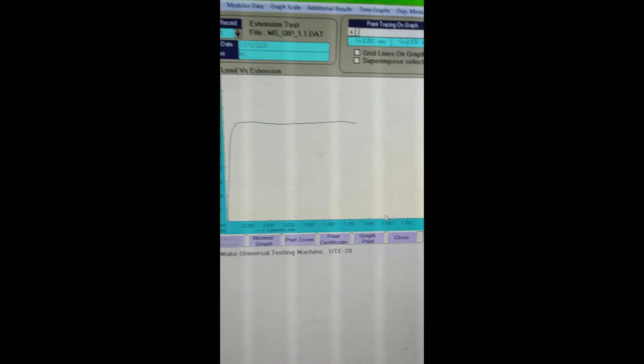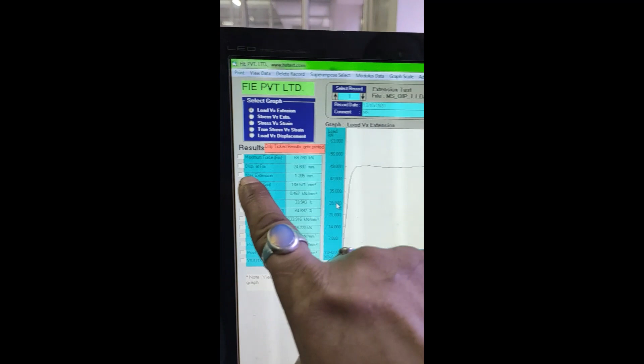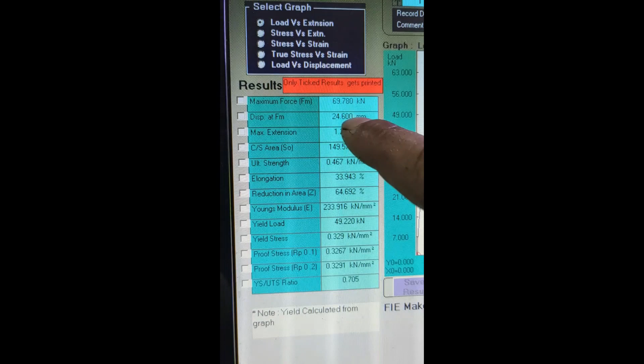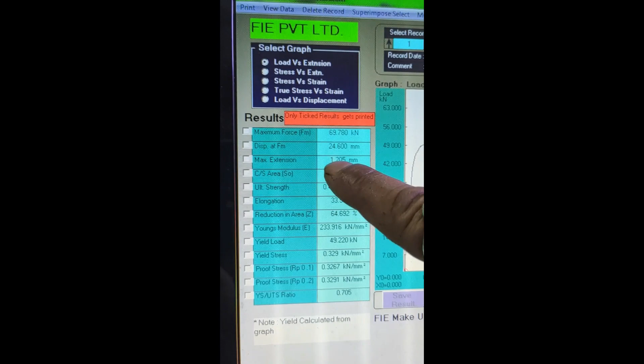This value we will put in, and we will put some MS, then we will close it, then the results will be saved. Now you are able to see the graph. So this is the graph, load versus extension. This is the maximum force, 69.780 kilonewton. This is the displacement at maximum force. This much displacement happened, the maximum extension as per the safe limit of the extension method.